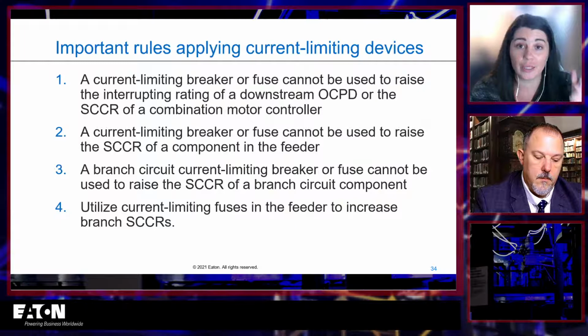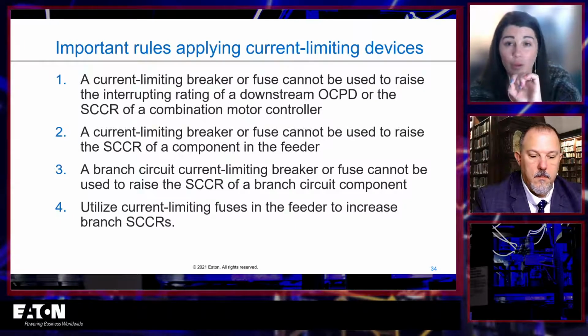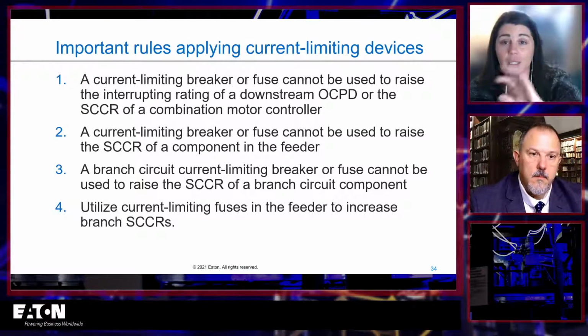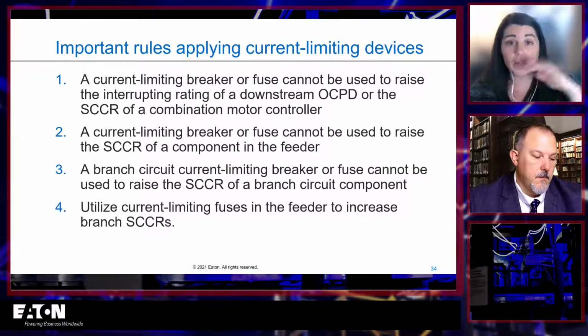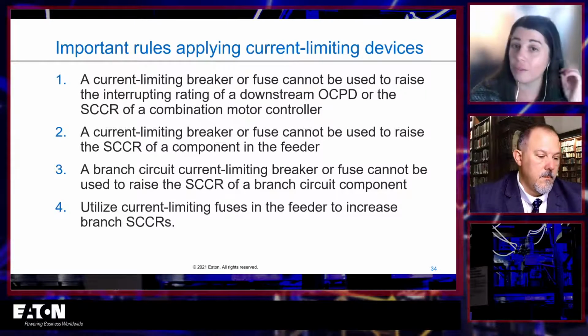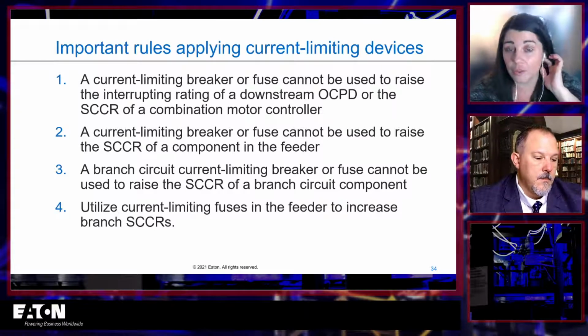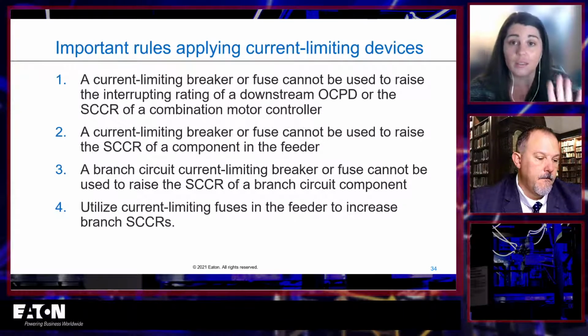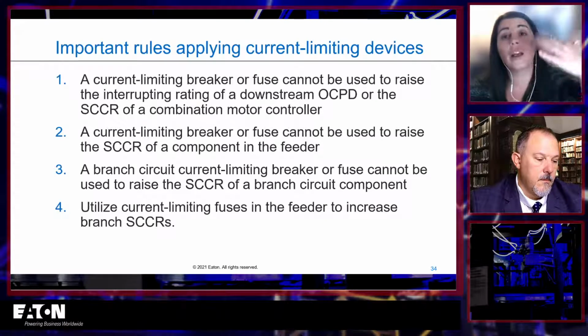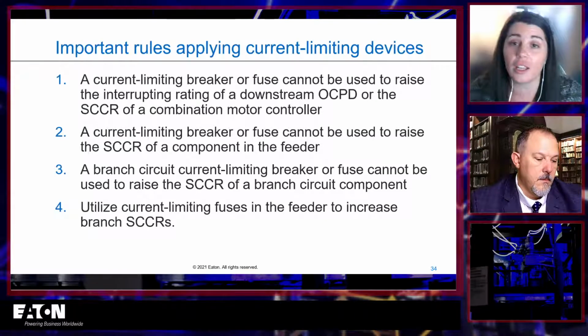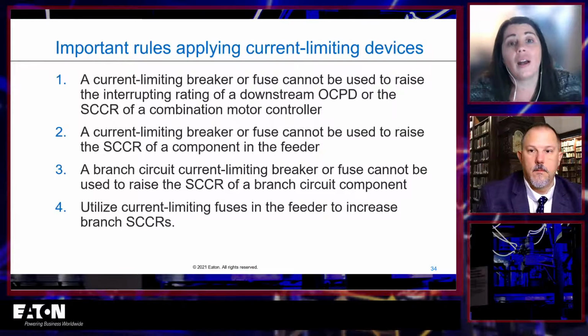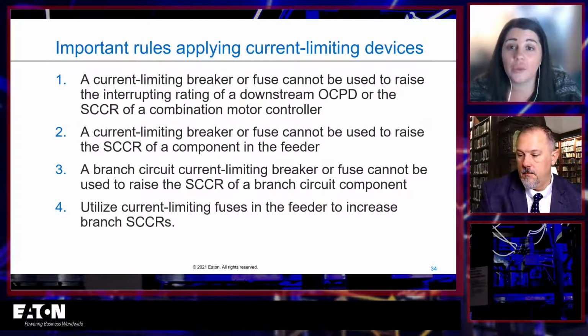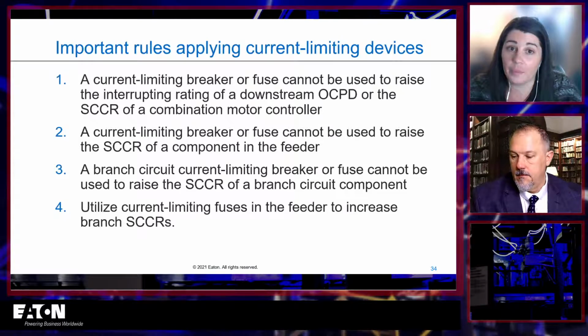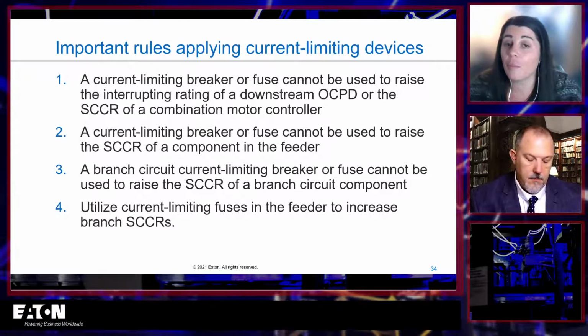So, right, when I said it was that specific part number of combination, so this plus this plus this, and it has a rating of this, that's what it is. And again, it doesn't matter if you put a current limiting fuse in front of it. You cannot use the logic of putting a current limiting fuse in front of it to raise the SCCR any higher. And this is only a way to increase short circuit current rating of a device in the branch.